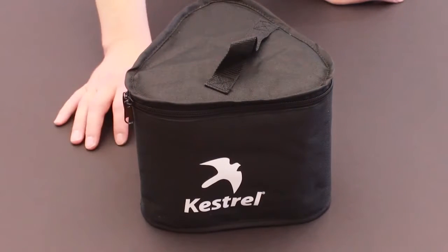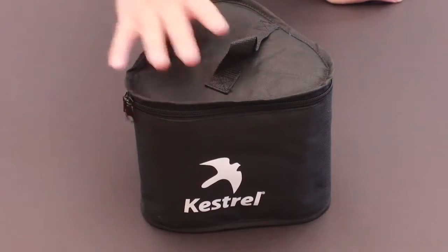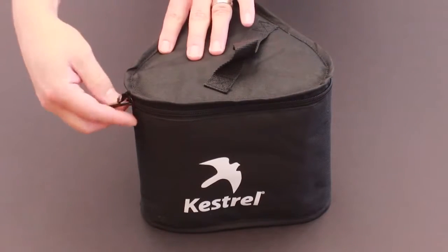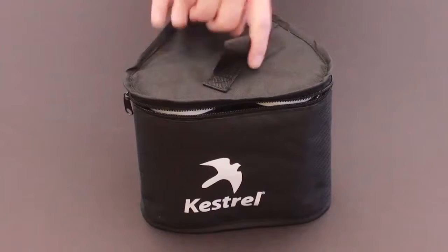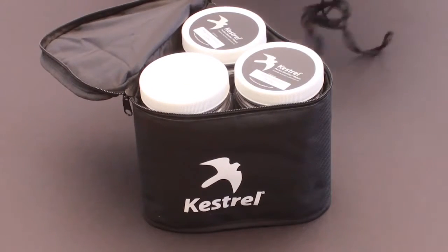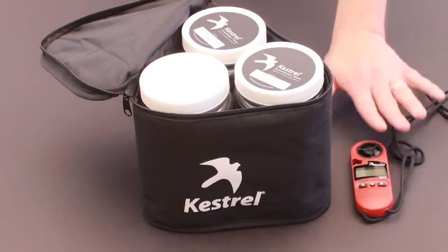After a suitable amount of time has passed, we recommend 10 hours. This will all be at the same temperature, and we can start the process to do the calibration. Now, open it up, and we are going to start with a Kestrel 3000 series.